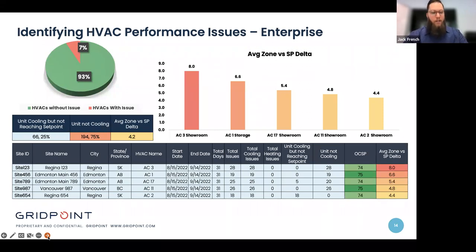So of the units that had an exception during this reporting period, 75% of those units were not cooling. So that's your go-to list to find out, hey, where do I need to prioritize my service tickets? And if I'm having a tech on site for PM, which units should I have them focus on first that we know already have confirmed mechanical issues on site, or unit not responding the way we expect it to.